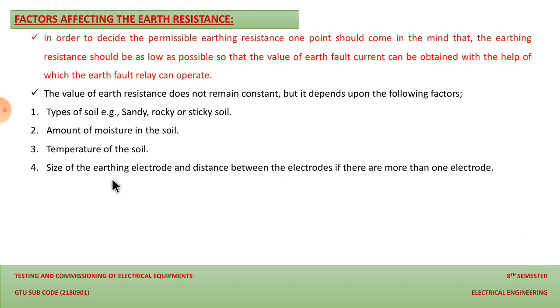And then the size of the earthing electrode and the distance between the electrodes. This is again a major factor that affects the earth resistance. If there is more than one electrode, then we should keep in mind the size of the earthing electrode and the distance between the electrodes. According to our requirement, we can place n number of earth electrodes, and we can keep a specific distance between electrodes to maintain a proper earth resistance of the soil. And the depth of the electrode under the ground is again a major factor. If we do not get a proper depth, then we cannot maintain the earth resistance properly. So we have to pay more attention to maintain the earth resistance of that area.